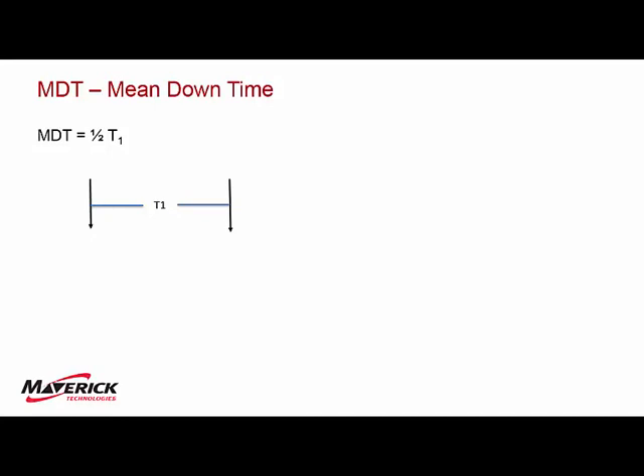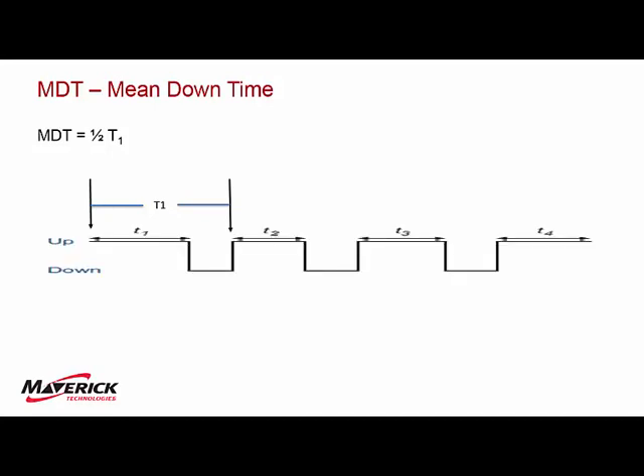Unavailability is your failure rate of undetected failures times your mean downtime. Undetected failures are failures that you don't know happened. It's that level transmitter stuck. When the level goes high, your tank can overflow because it's still stuck, but you don't know it until it happens. That's going to lengthen these things. Mean downtime winds up being half, on average, half of the time between when you test something. I install it. Everything's running great. Life's good. It breaks, but I don't know it broke. Then I either test it or I need it. In this case, I test it and I find the failure. Now I'm back up and running. On average, it's just as likely that it's going to fail at the beginning than in the end. There's a constant probability of failure. It might fail here sometimes, it might fail here sometimes, but on average it's going to fail in half the time. You can use half of your proof test time to give you this mean downtime.